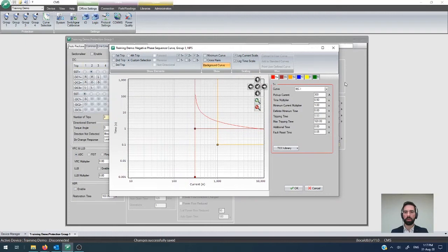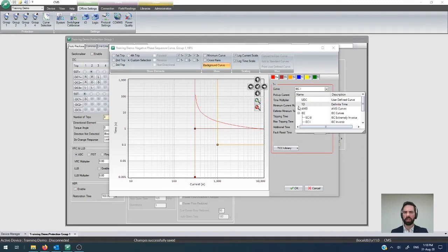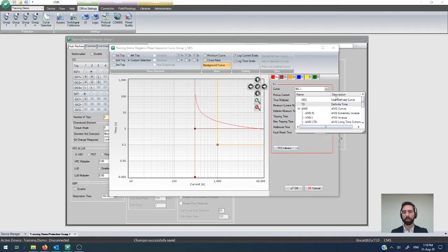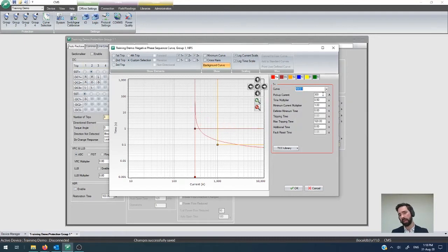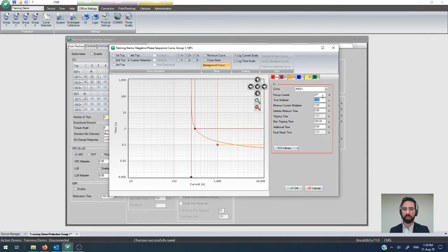If we wanted to configure these individual ones, we can drill into them by clicking on them, and it brings up the curve map. It's something that's very simple for us to be able to configure. Usually you will have these protection settings on hand as to what you need to configure. You might have a specific curve that you need to add, a pickup level of whatever that configuration is for your feeder, and then you can go ahead and punch in those numbers, click OK, and it is committed to the configuration file.